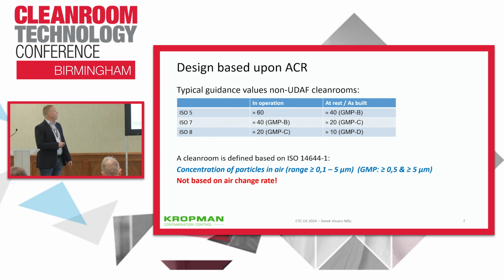Here I show you some typical guidance values we are used to in the Netherlands. For example, if I take a grade B clean room, ISO 7 in operation, we design it at 40 air changes per hour, and grade C, 20 air changes per hour. However, a clean room is not defined based on any air change rate. If we look at the definition of a clean room, it's primarily based on the concentration of particles in the air. So why do a lot of our clients and also consultancy companies still write down the number of air changes in the user requirement specifications? We as Kropman always say, please write down the ISO class or GMP grade, and then we calculate for you how much air is required.